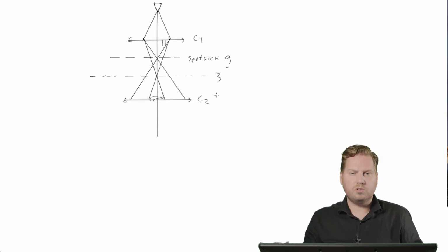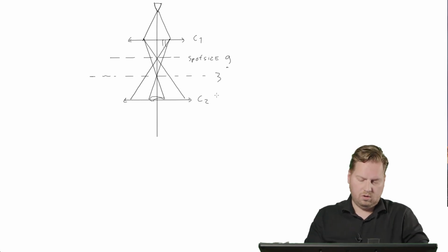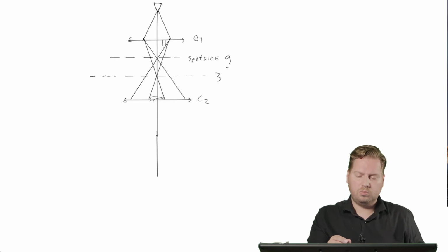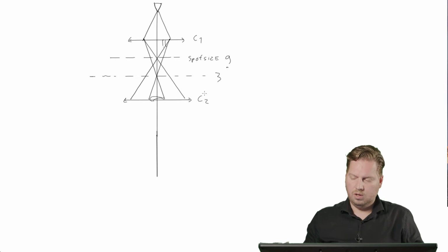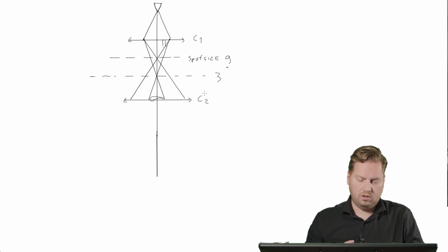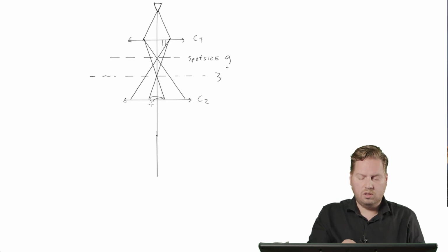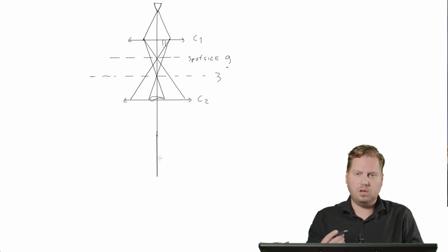Now when the microscope is aligned, what we make sure of is that when you change the spot size, you see that the current, the percentage going through the lens, changes on the microscope for C1. But you also see a change, be it small, in C2. Because if you change spot size, you don't want to have a different projection, a different spot on your specimen. You want to have that the same. You only want to change the spot size and nothing else.